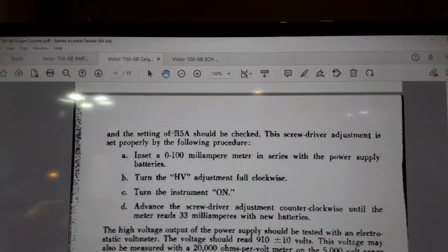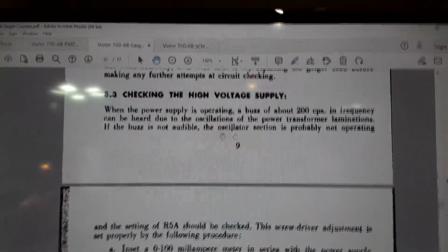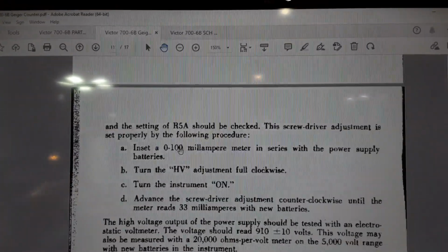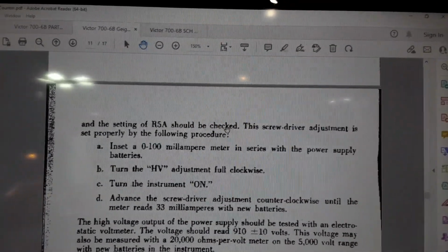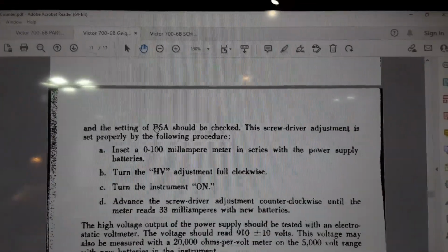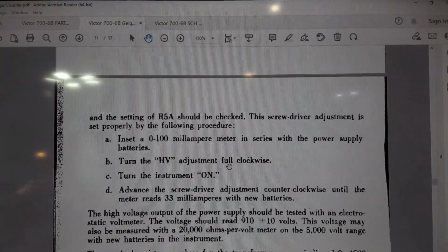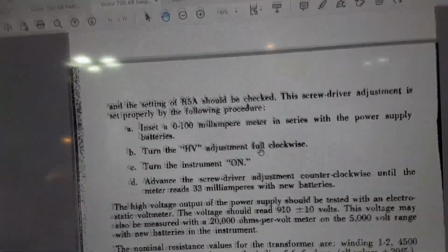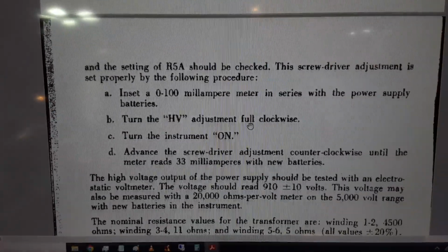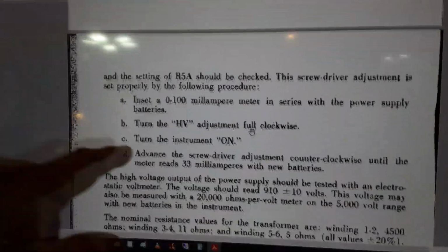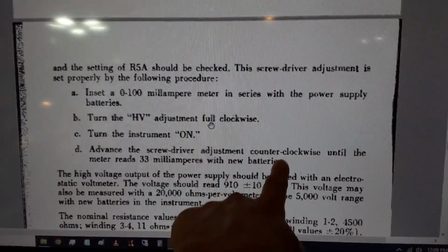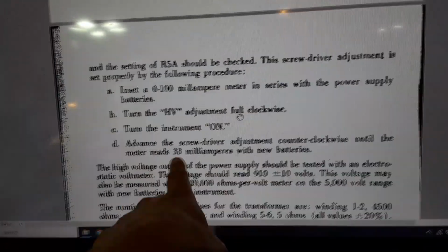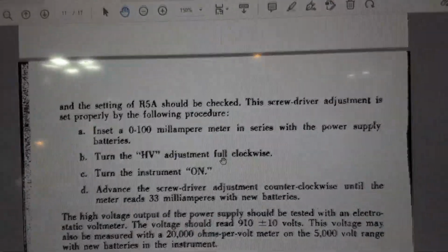And so we need to set the high voltage potentiometer or calibration control so that we turn it all the way on, fully clockwise, full high voltage, and then we back it off, and we advance the screwdriver counterclockwise, so we back it off until we get 33 milliamps with new batteries. Well, these are new batteries.